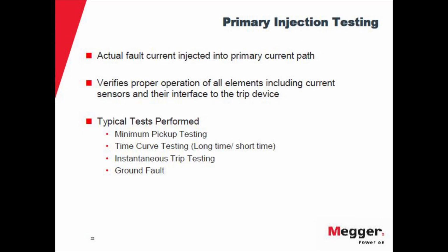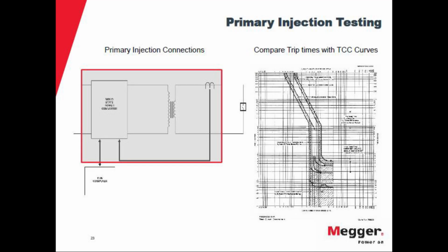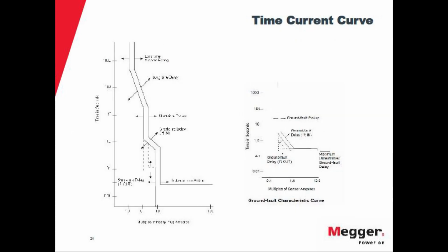The minimum pickup testing is when the protection element will actuate or start operating. The manufacturer tells you that it should operate in this band or this other band, depending on the breaker settings. So a traditional difficulty in testing circuit breakers is interpreting these curves, getting the actual operating times from the curve, and knowing what current to inject.